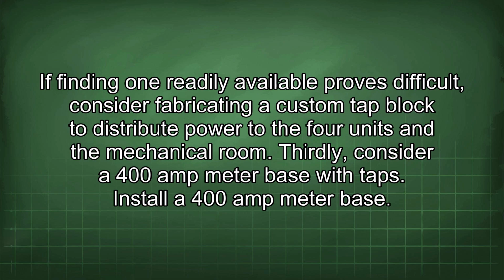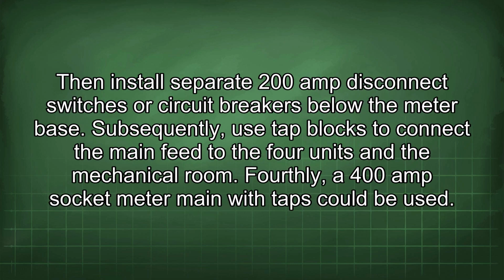Thirdly, consider a 400 amp meter base with taps. Install a 400 amp meter base. Then install separate 200 amp disconnect switches or circuit breakers below the meter base. Subsequently, use tap blocks to connect the main feed to the 4 units and the mechanical room.